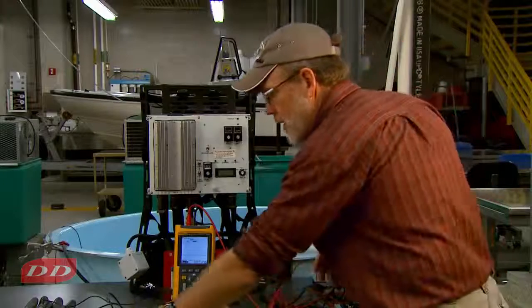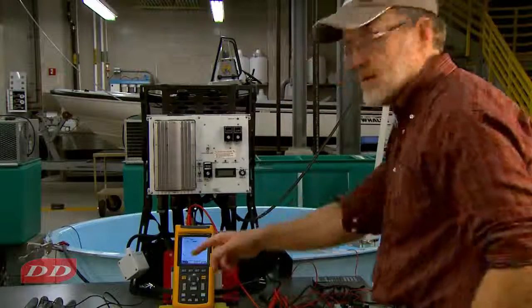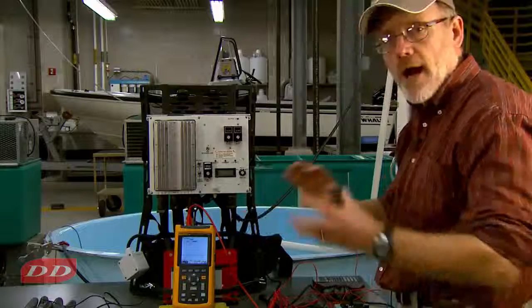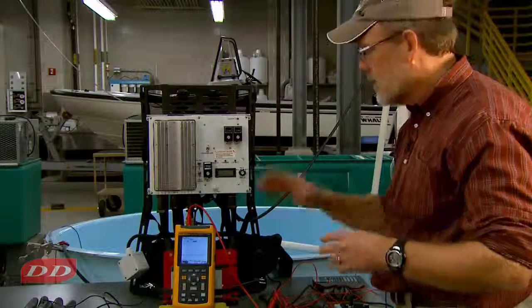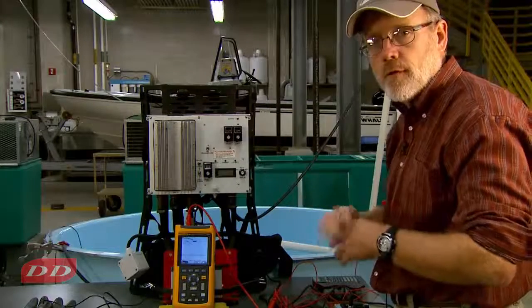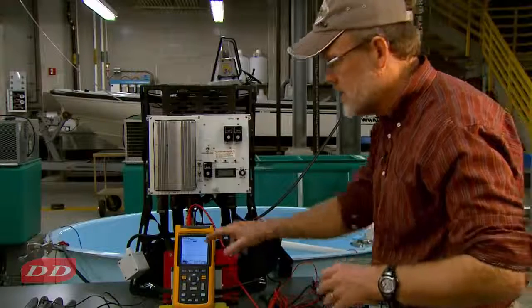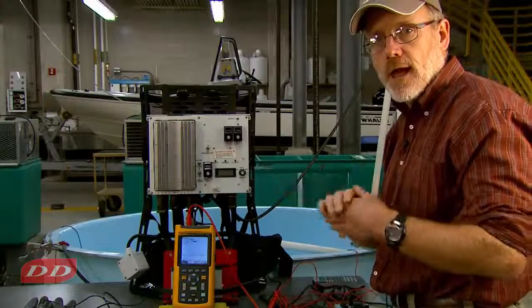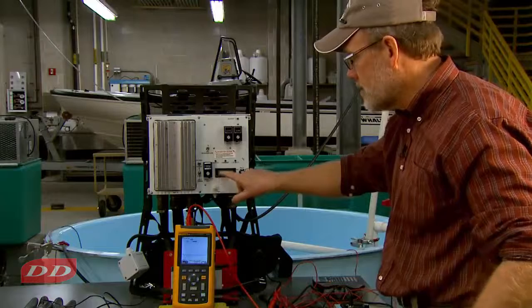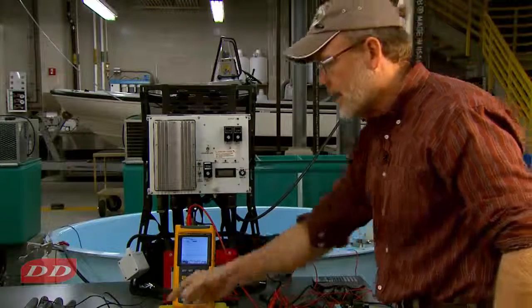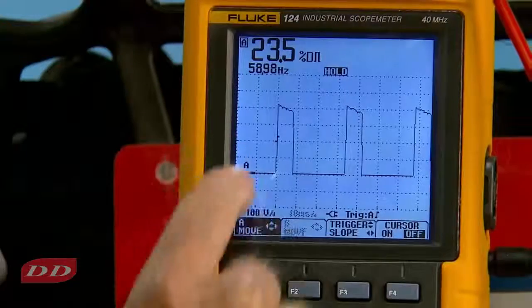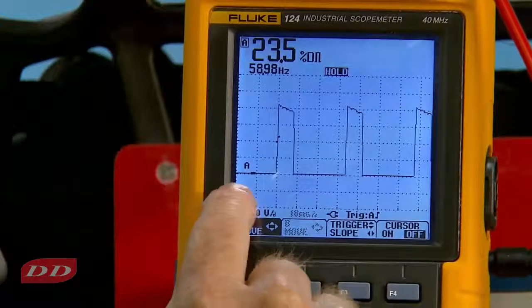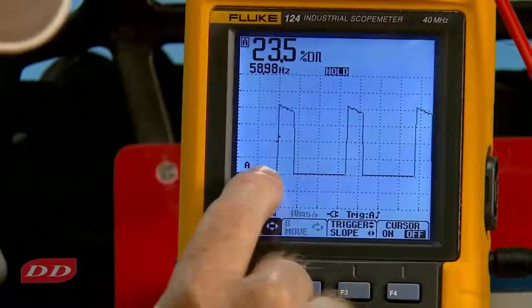And so what I've done is I've replaced the multimeter with the scope meter, and we're actually going to look at the waveform. So we're going to apply 450 volts again, or try to catch the waveform and see exactly why there might have been a discrepancy between the voltmeter reading and the multimeter reading. So we've captured the pulse DC waveform at the 450 volt setting.